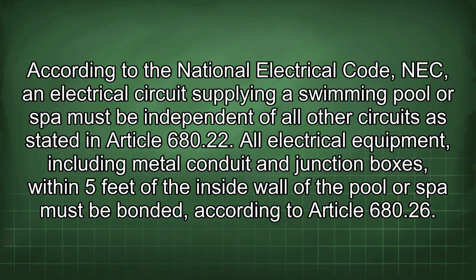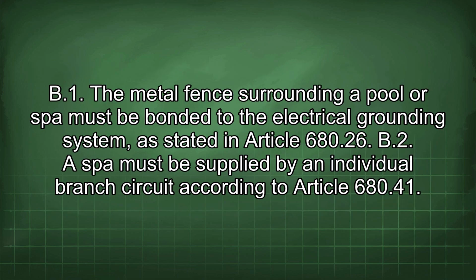According to the National Electrical Code, NEC, an electrical circuit supplying a swimming pool or spa must be independent of all other circuits, as stated in Article 680.22. All electrical equipment, including metal conduit and junction boxes, within 5 feet of the inside wall of the pool or spa must be bonded, according to Article 680.26. B.1.